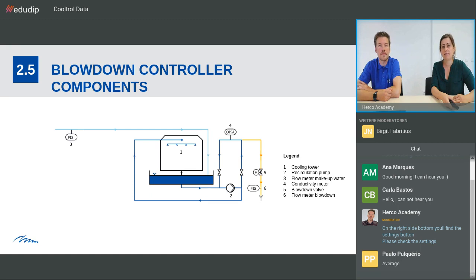And we have also here the line in orange, which is really the blowdown. You can see with the number 5, the blowdown valve, motorized valve, which is activated or deactivated by the blowdown controller. And you see there is also usually a flow measurement on the blowdown line so that you know how much water has been used.